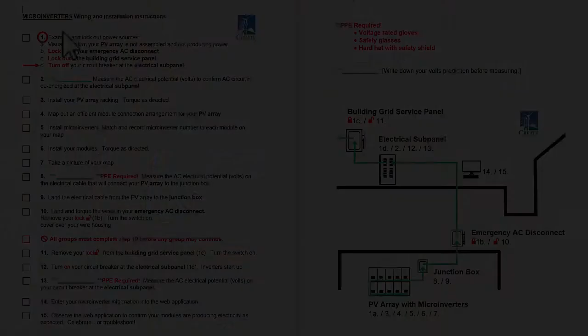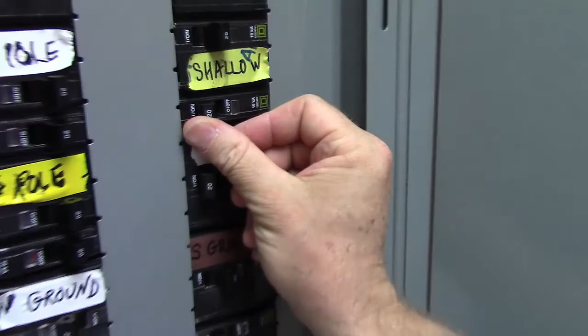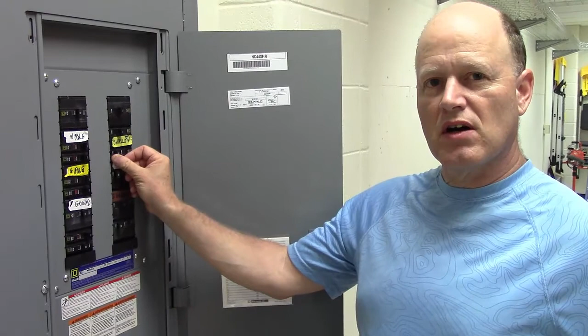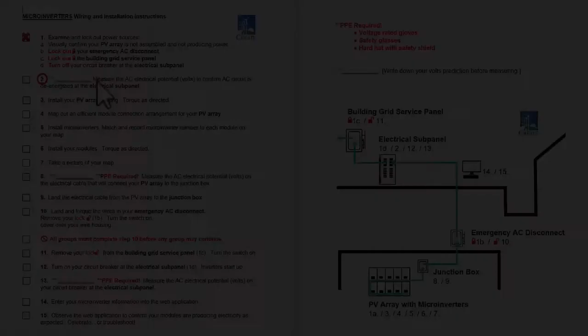And 1D, turn off our circuit breaker at the electrical sub-panel. I'm shutting off the circuit breaker at the electrical sub-panel for the PV system that we're working on. Step 2 is to measure the AC electrical potential in volts to confirm the AC circuit is de-energized at the electrical sub-panel. That's right here. And before we do this, we write down our volts prediction, and our prediction is 0 volts.